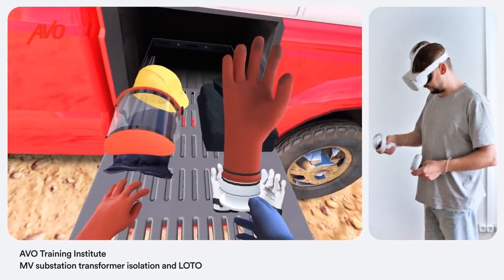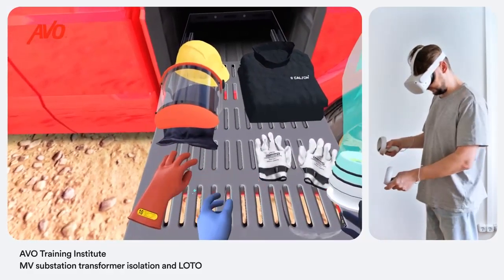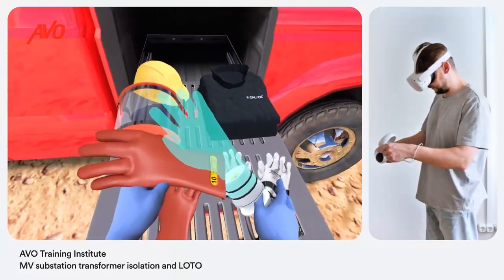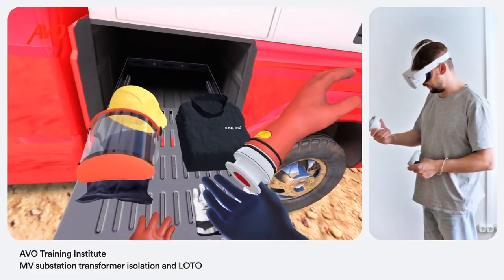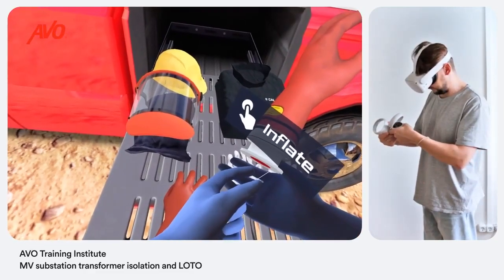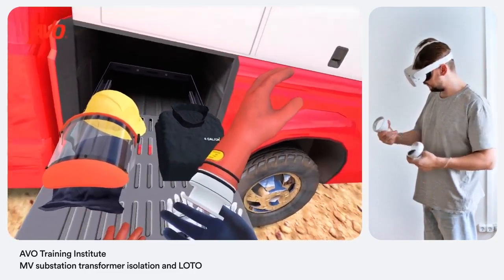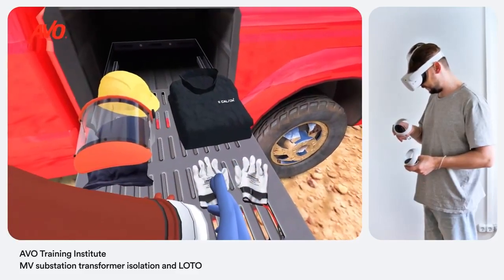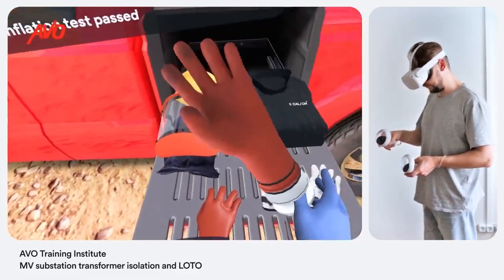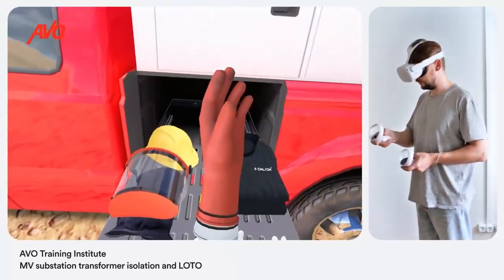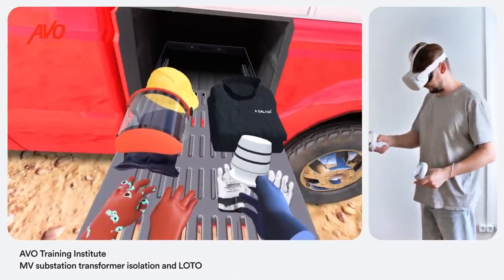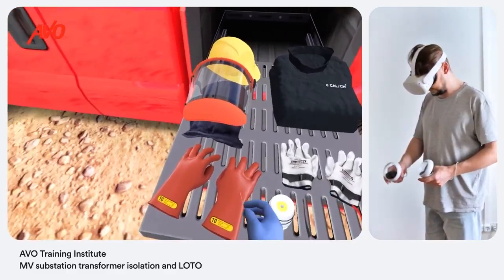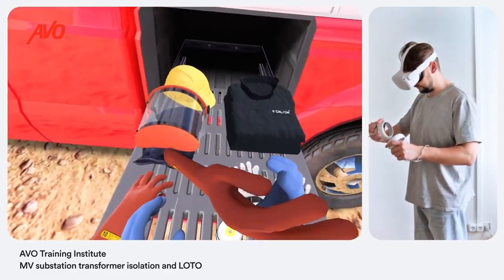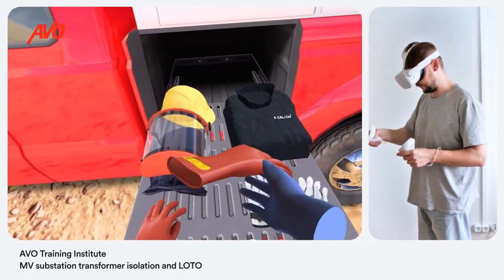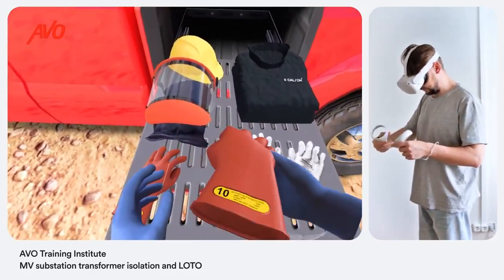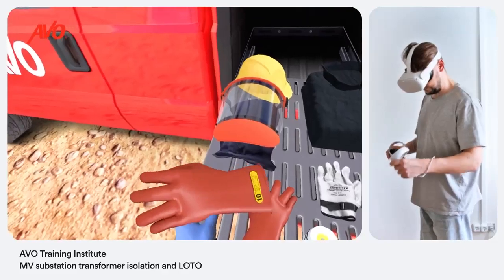Slide the other glove over the inflator. Inflate the glove using a push button at the bottom of the portable inflator. Hold the glove up to your ear and listen and feel for any air leaks. All insulating gloves must be visually inspected after inflation and before each use. Always inspect both the outside and the inside surface of each glove. Pay special attention to the base and tips of the fingers and thumb. Pull them apart looking for any irregularities.